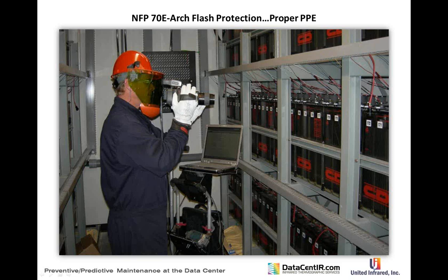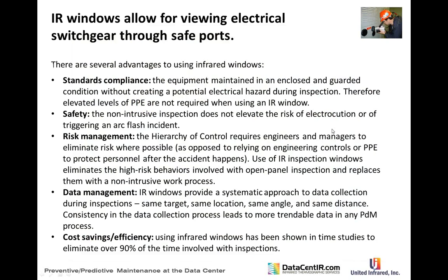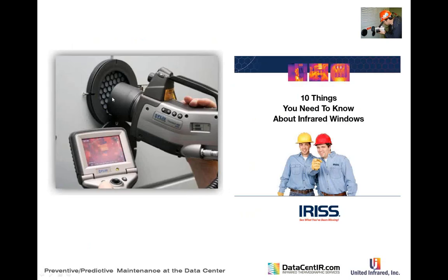We have a partner company, IRISS, that manufactures infrared windows. You can install these IR windows in a panel and check equipment during normal business hours — 8 to 5 — instead of requiring a maintenance window, which in data centers is usually midnight Saturday to 6 AM when the data center is idling.